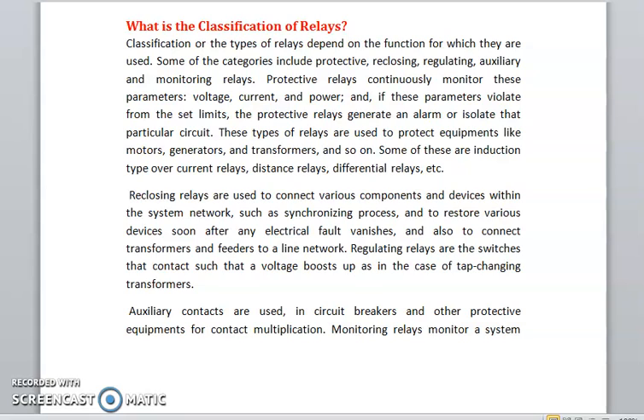What are the classifications of relays? Classifications are the types of relays depending on the function for which they are used. Some of the categories include protective, reclosing, regulating, auxiliary, and monitoring relays. Protective relays continuously monitor these parameters: voltage, current, and power. If these parameters deviate from the set limits, the protective relays generate an alarm or isolate that particular circuit. These types of relays are used to protect equipment like motors, generators, and transformers, and so on. Some of these are induction type overcurrent relays, distance relays, differential relays, etc.